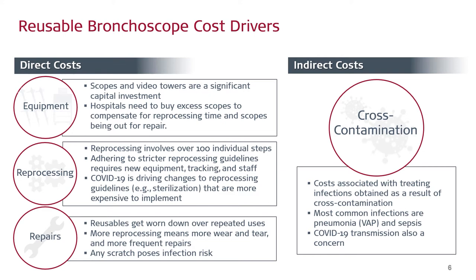It's also important to remember that guidelines for reprocessing are becoming stricter and more intensive over time, and that's also a cost driver. If you're moving from, say, single high-level disinfection to double high-level disinfection, or even to sterilization as you get into more advanced reprocessing methods, the costs go up.